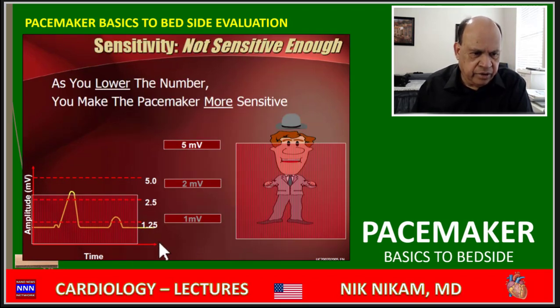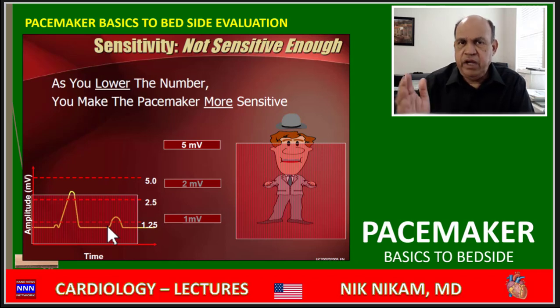They are separate, that's what we need to keep in mind. For ventricular activity, you want to make sure the signal is closer to 5, not 0.1, not 1.25. If you set it too low, it may pick up muscle signals, muscle tremors, something like that, and it may get confused and start pacing at a very rapid rate, which you don't want.